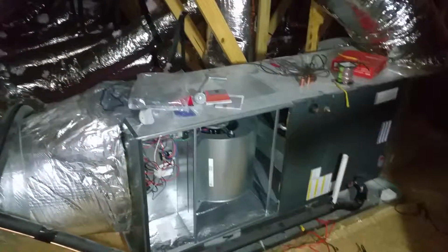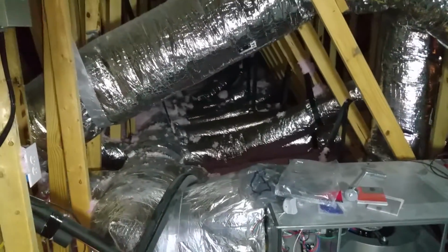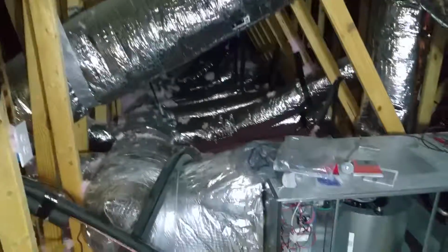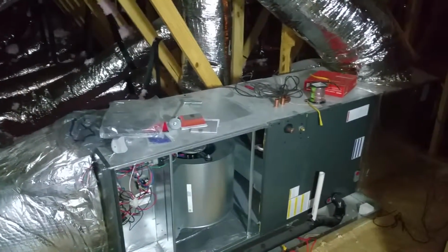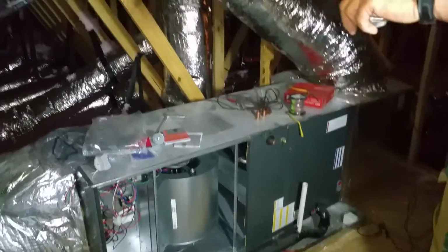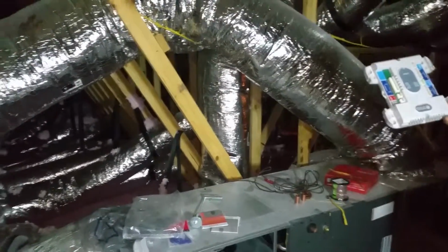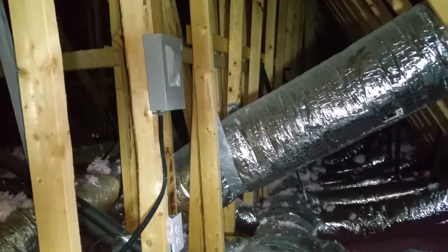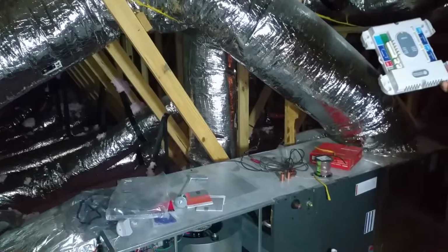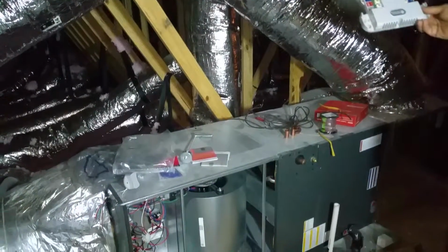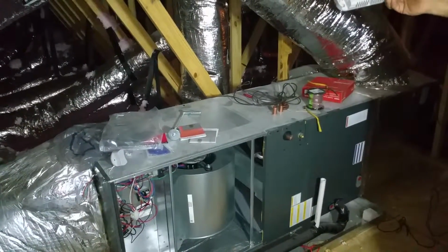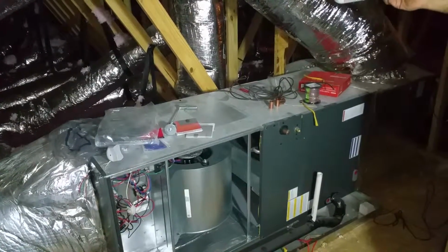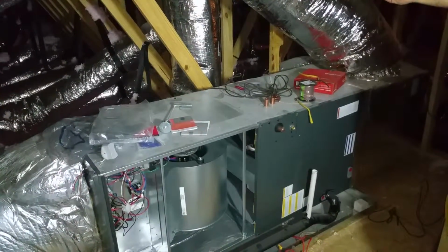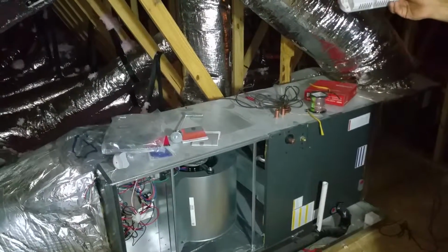And we installed all sheet metal trunk line. We don't believe in fiberglass ductwork. Sheet metal you could clean later. We externally wrap it. There's no insulation at all in the airflow. We use motorized dampers for the zone control. We put a barometric damper on the top over here to help relieve the air pressure for when the secondary zone calls. And it's a very low maintenance product. Once you're done with this air handler, you shouldn't have to touch it as long as you keep the filters clean. This should run a good 10, 12 years without any problems.